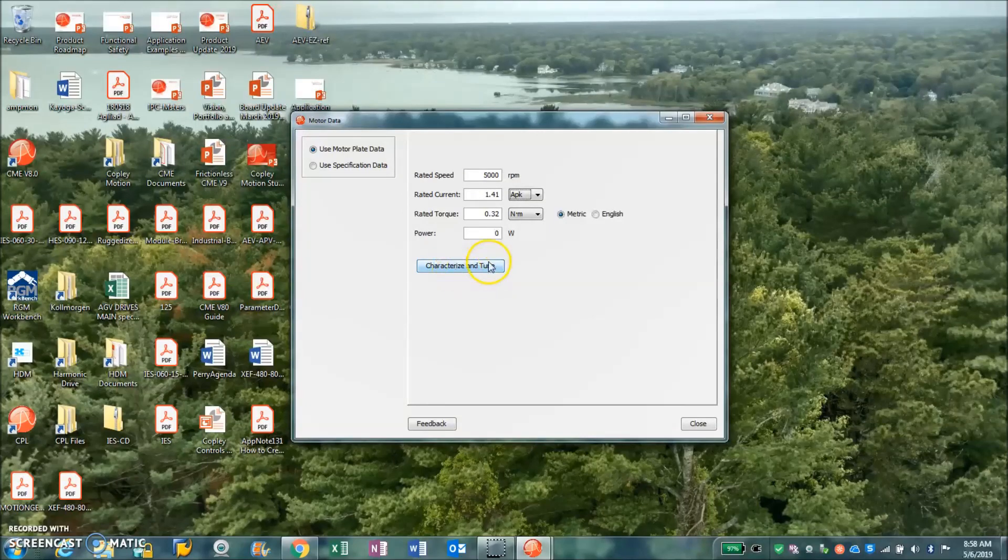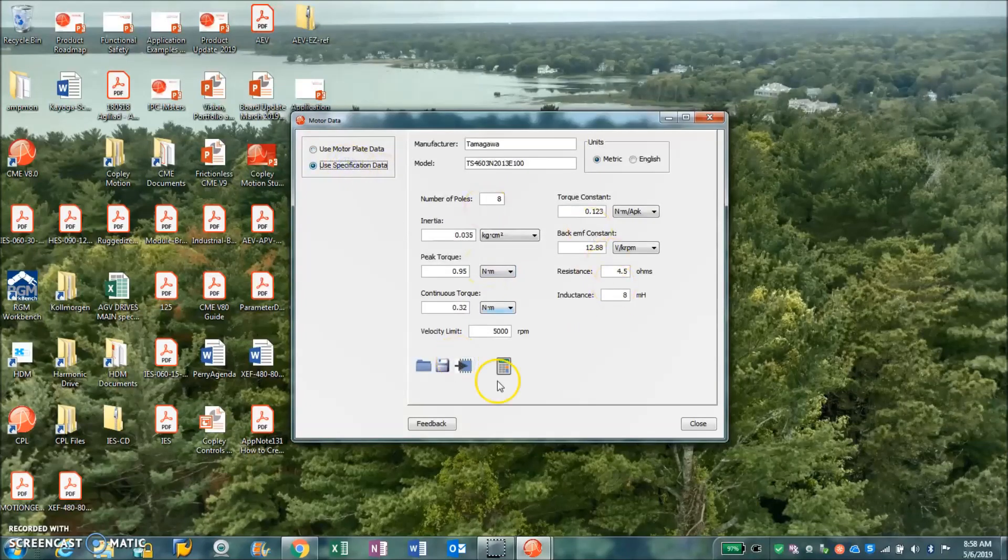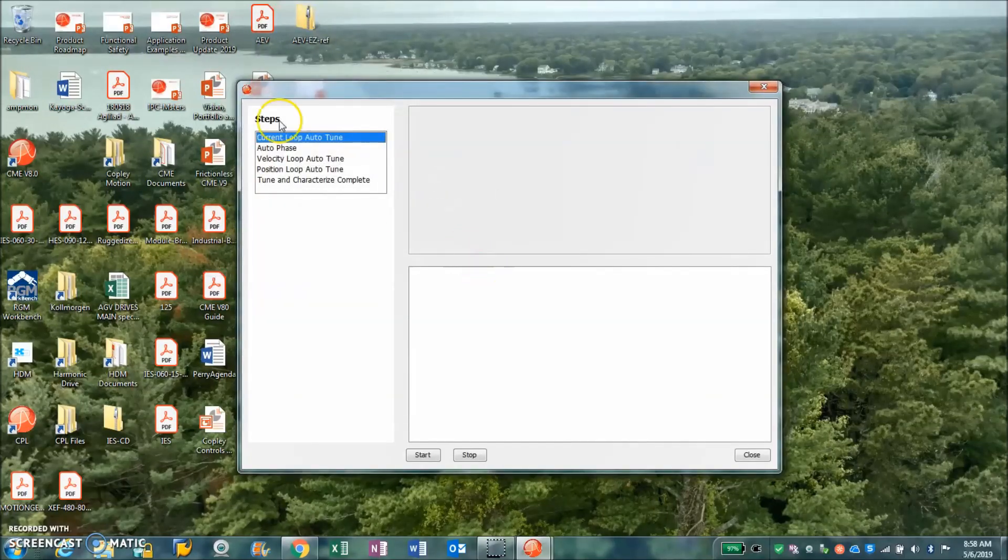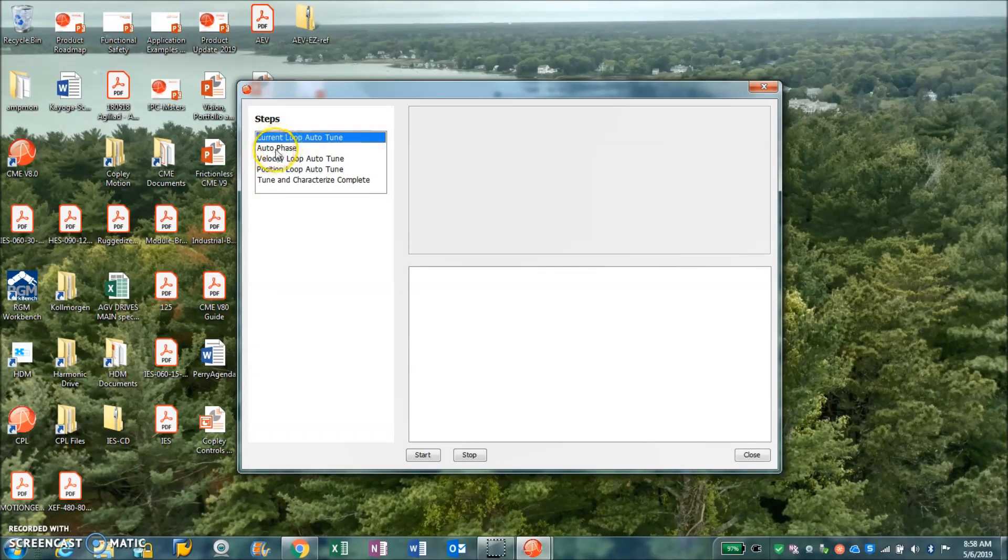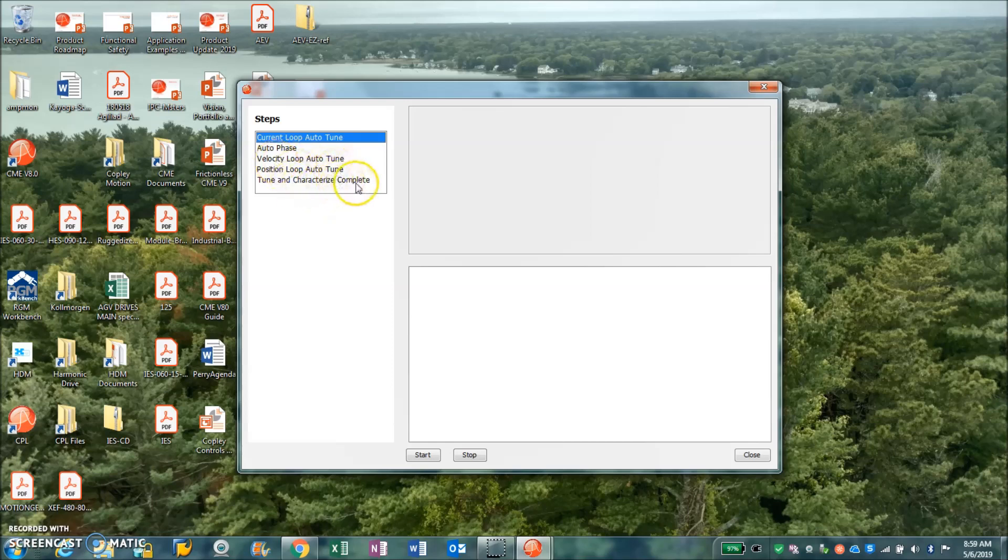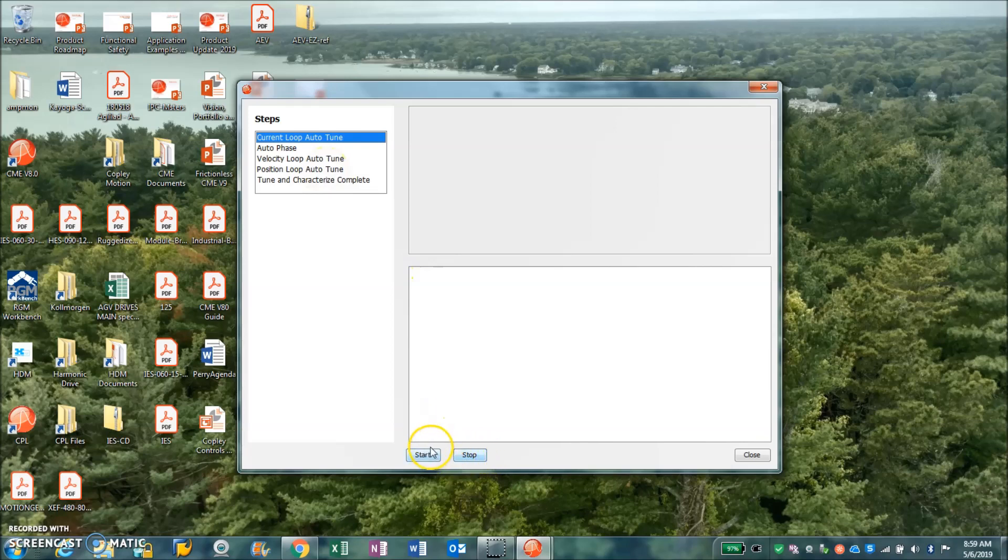Part of this advanced feature set is that you can do characterization of the motor given minimum data. I still like to get all the motor data, but sometimes we're stuck with a motor we can't get it all. So we can do this characterize and tune, and it does stuff like tune the current loop, auto phase, tune the velocity loop, tune the position loop tuning characterize. I think we still need to work on the position loop tuning - it just takes the default value. So if you have a large inertia mismatch, just be careful. You want to make sure you still tune the position loop manually, but I'm sure 8.1 will have some new features for that.